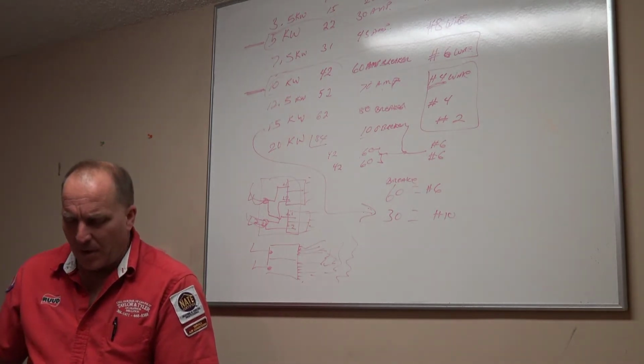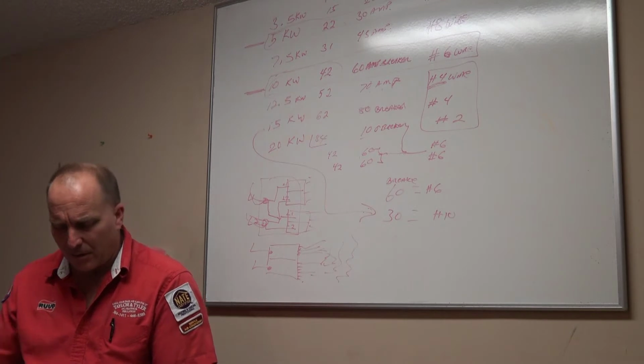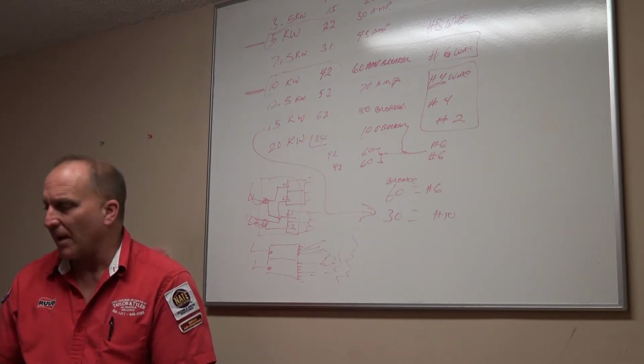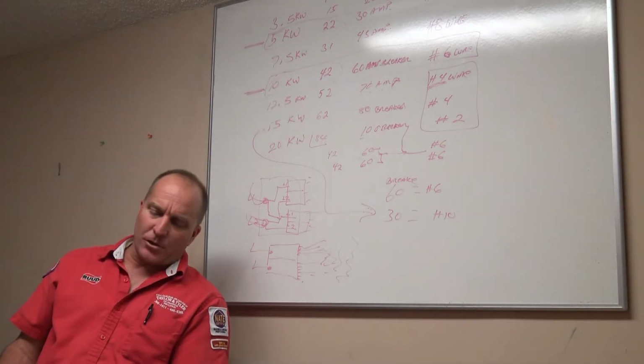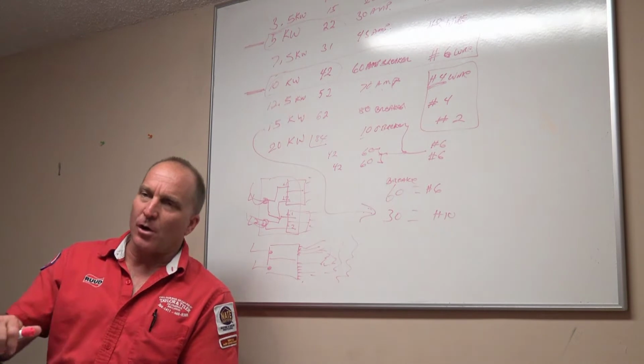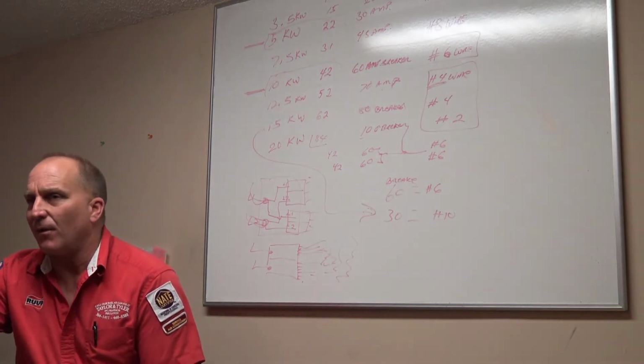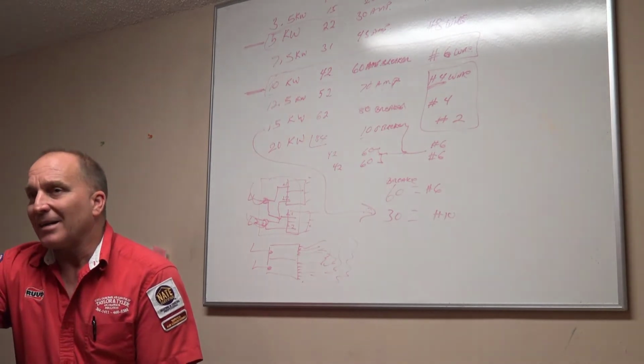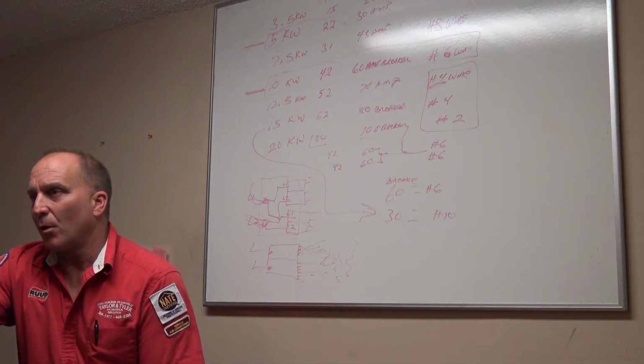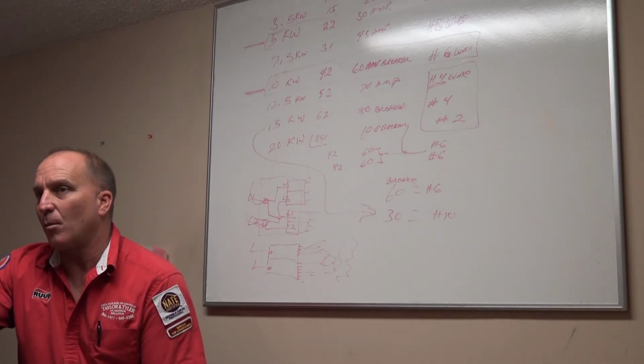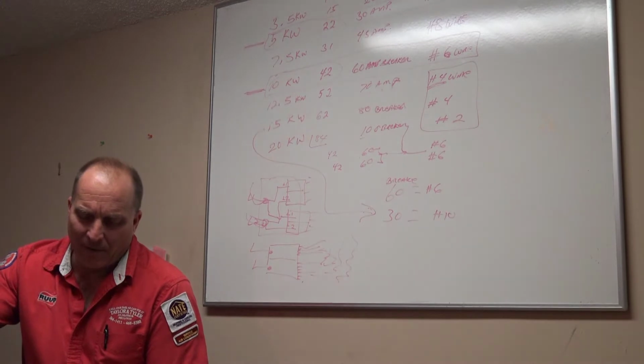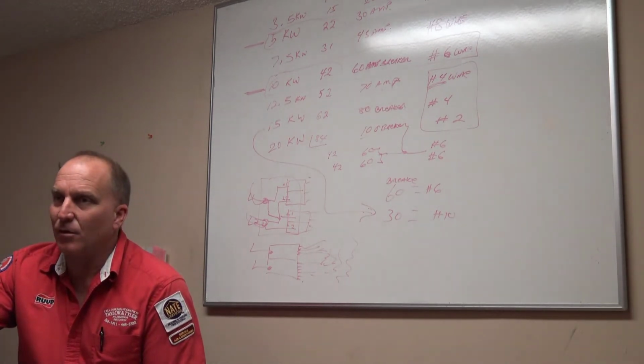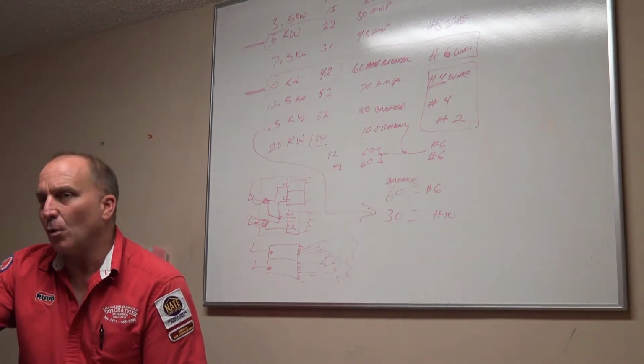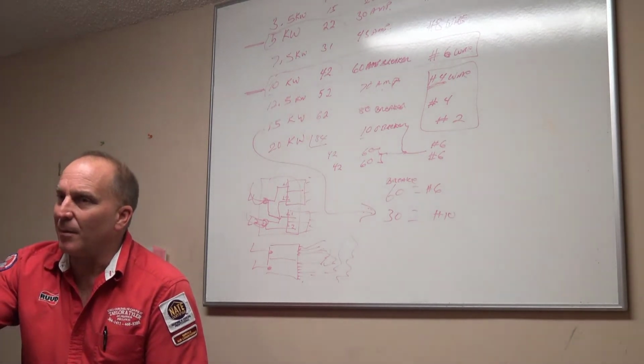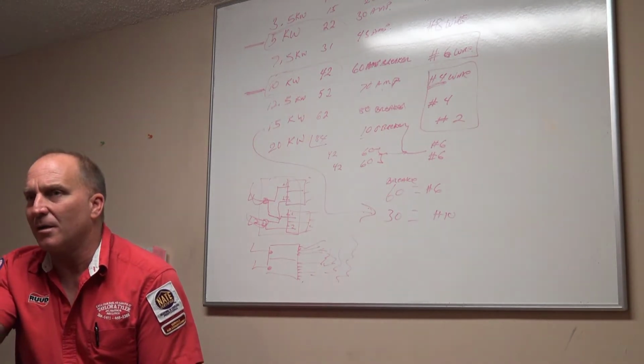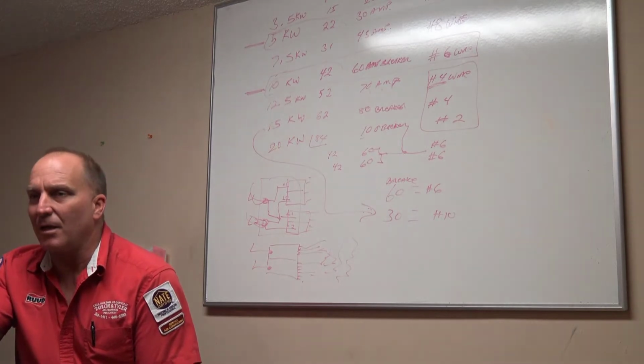Limit switches is number 8. We are dealing with electric heat systems in this particular video here. And limit switches is absolutely your most important switch on an electric heat system, because it is your only safety device on an electric heat system. A gas furnace has rollout switches, limit switches, blower motor switches, negative pressure switches in order to help prevent fire, right? Well, here we have one limit switch that is protecting your system. Because the heating element just gets voltage to it, and the resistance of the heating element just energizes that heating element is all it does, and it lights up and it's glowing because of the heat on it, right?